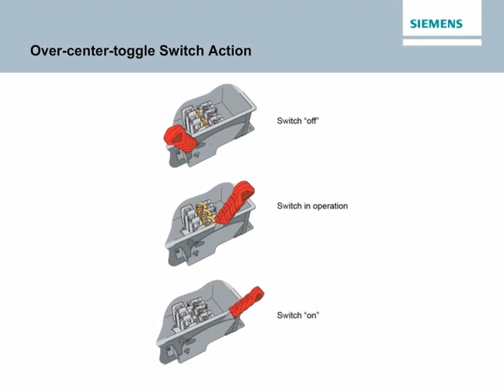The VB2 cover interlock prevents someone from opening the door while the switch is in the on position. Normally, the interlock also prevents someone from turning the switch on with the door open. However, for the purposes of testing or servicing, the door interlock is defeatable. As shown in the accompanying illustration, this can be done with a normal screwdriver.